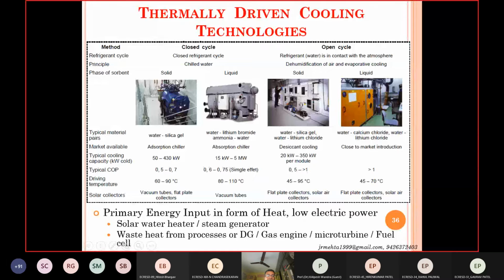When you're talking about the closed cycle, this is adsorption and this is absorption. So adsorption, one of the options is water silica gel, and the typical COP that you can expect. So COPs are somewhat lower, but the driving temperatures are also lower. And if you talk about this part, the water lithium bromide or ammonia water, the COPs given here are for single effect, right? Like in what sizes they are generally available commercially.